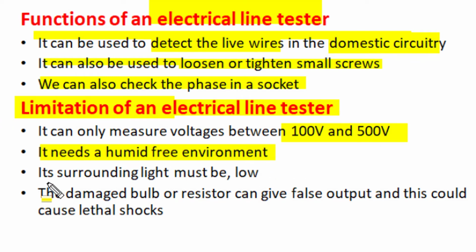Though our neon bulb is very sensitive and gives good enough light output, when the test current is quite small, the visible light can only be detected if the surrounding light is low. In bright conditions, the dim light of the neon tester may not be visible. So it needs low light surroundings for testing. Often a user has to cover the neon lamp a bit to get an indication when the surrounding light is high.